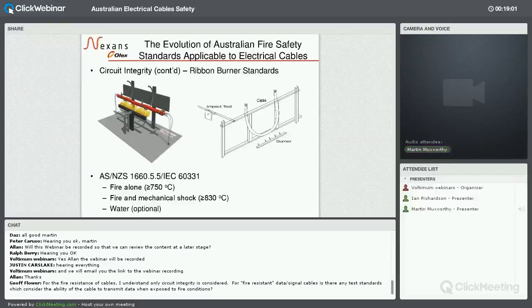Validation is done prior to applying a cable into the test setup. Thermocouples are used to ensure that the amount of gas and airflow rates, for example, that come out of the burner are adjusted to achieve the temperatures required. So that's validated before the test, and then the cable's put into position to actually proceed to do the test.